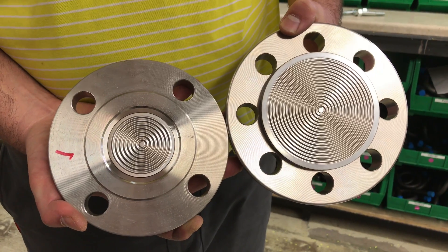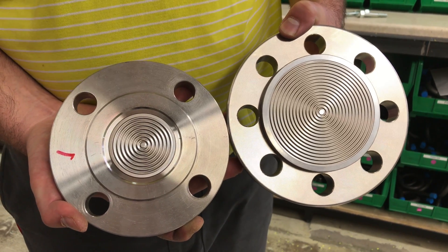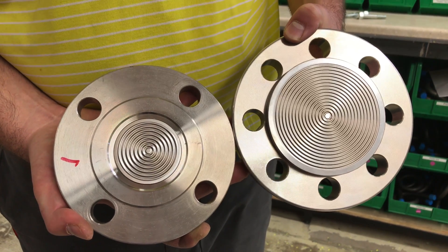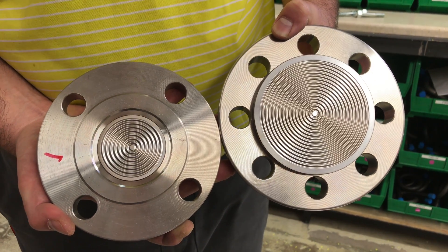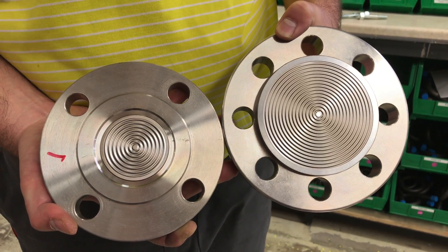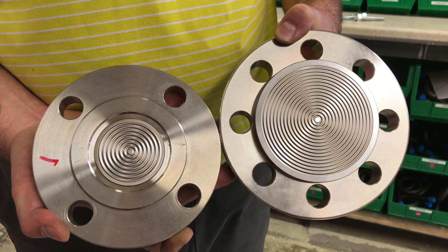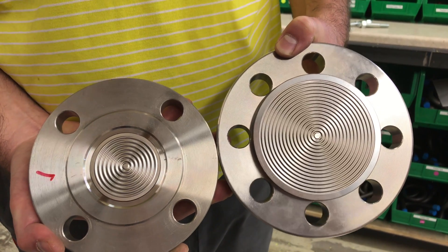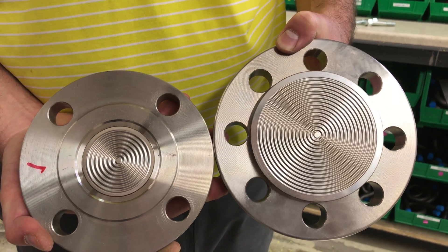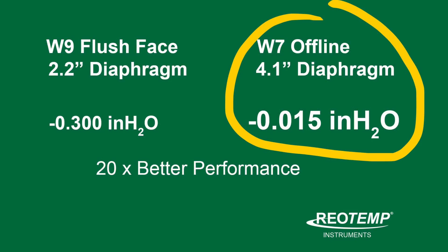The W7 with its 4.1 inch diaphragm has an effective surface area three and a half times larger than the flush face seal. That added surface area makes the diaphragm much more sensitive and more able to absorb fill fluid expansion without exerting a false pressure onto the transmitter sensor.